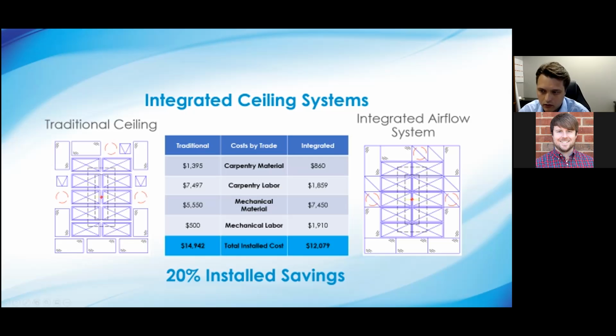If we're comparing two basically identical designs, but one has sheetrock crisscrossing through every component, so you have individual openings cut for every single device and big gaps between everything, versus one large ceiling opening with modular subsections and predetermined locations popped in there, that actually results in 20% lower cost. This is the primary reason why most of the country, except kind of the northern Florida, Georgia, Tennessee area, has adopted integrated ceiling systems, because they are less costly.